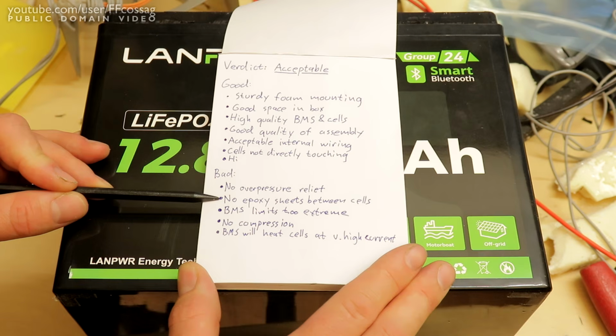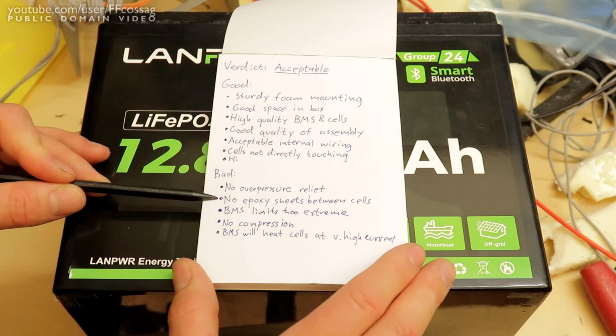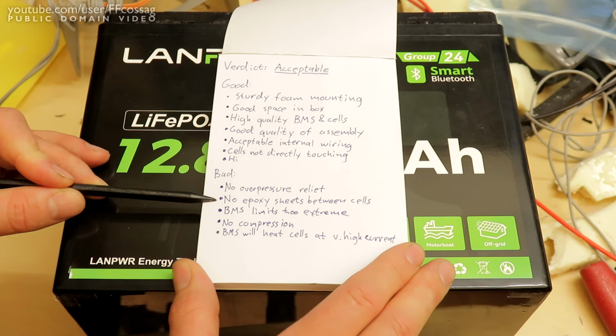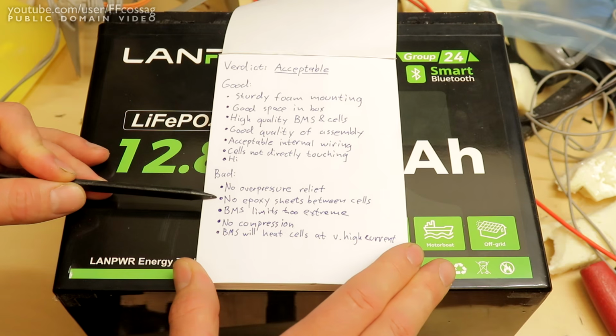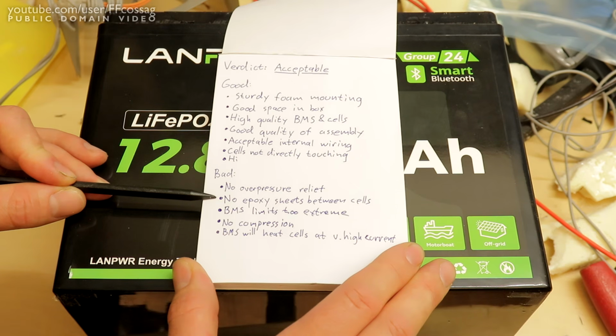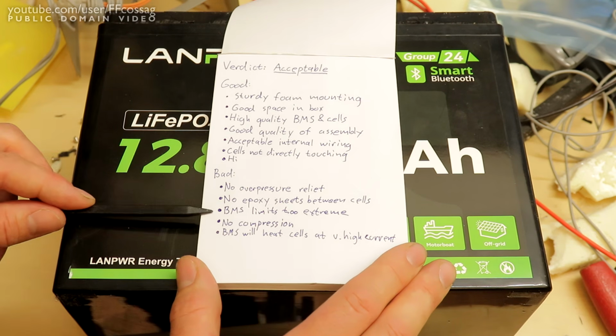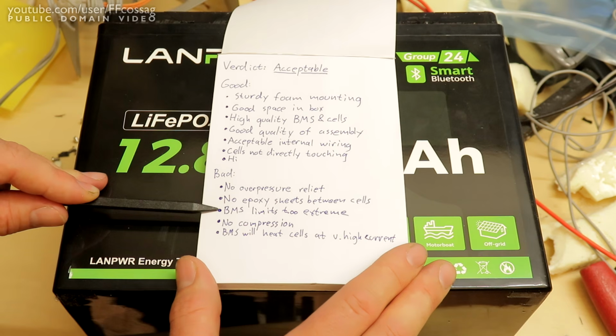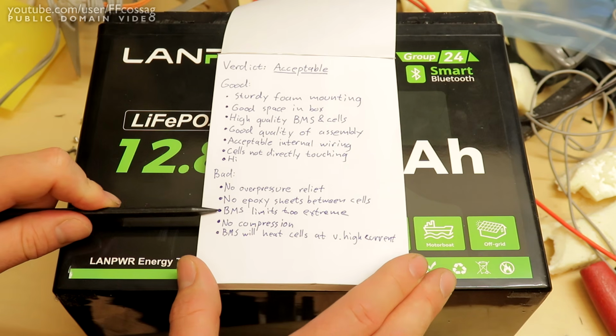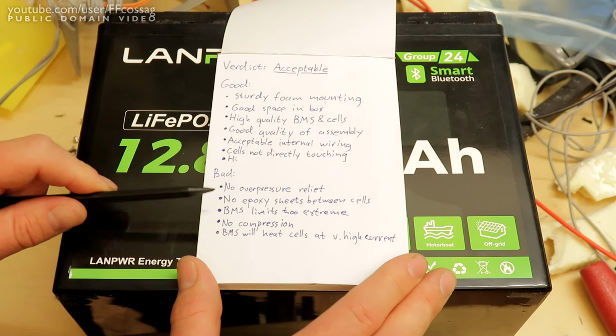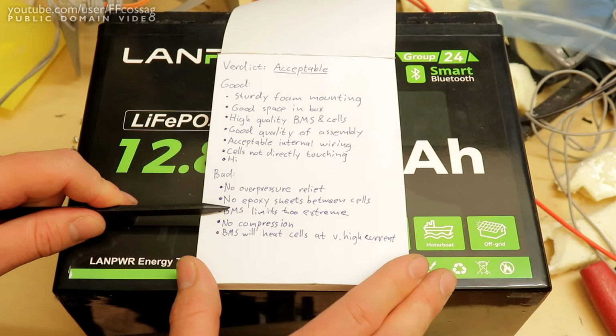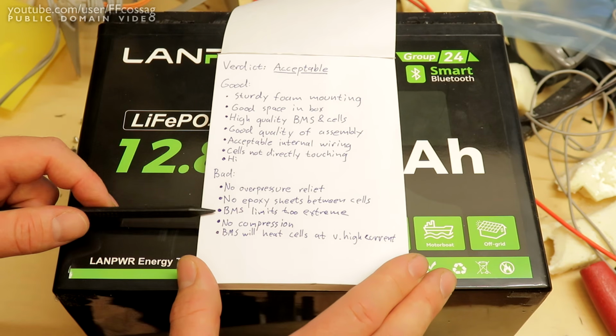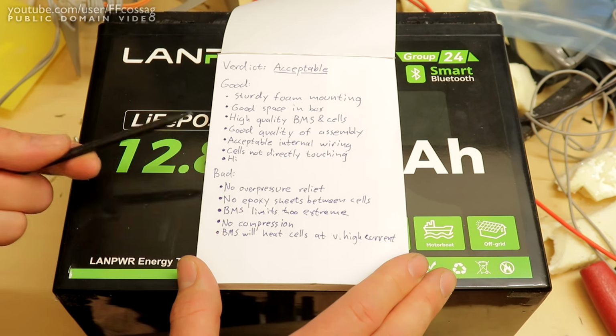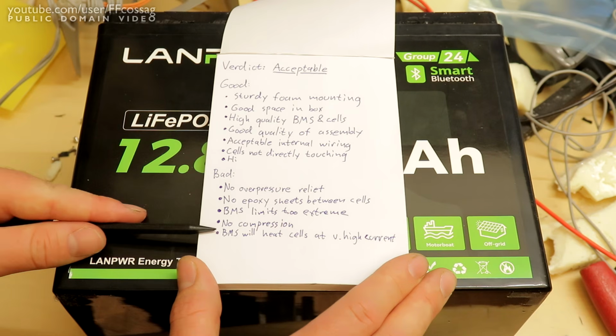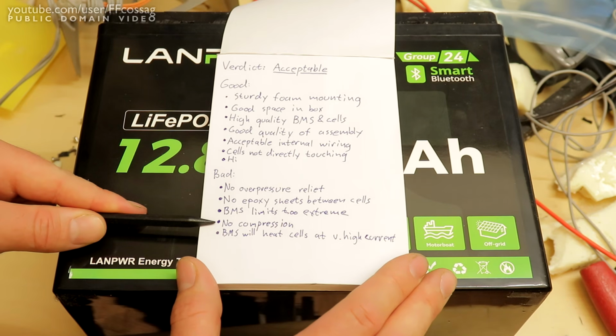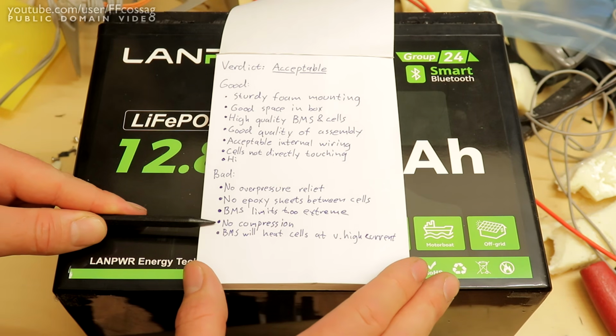There are no epoxy sheets between the cells. I would like to see epoxy sheets, because even though we have material between the cells, it seems to be some sort of soft adhesive type thing. The BMS limits are too extreme, 3.75 volts, it's not okay. I have to redact a point, because 3.75 volts OVP is too high, it is out of spec for the cells. Not okay. There's no compression, so that will limit the cycle life of the cells.